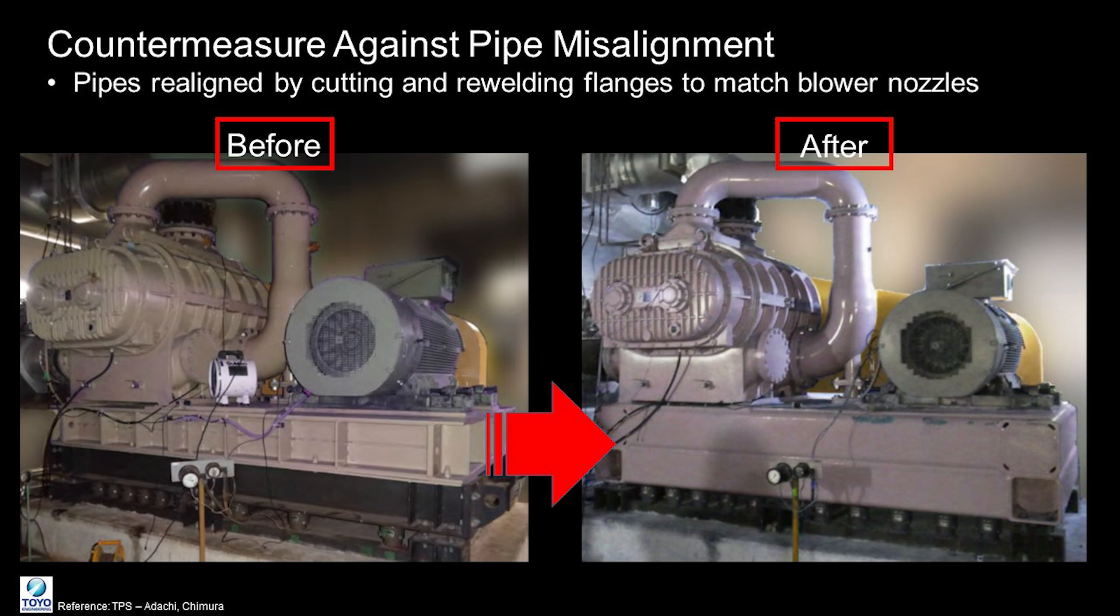To resolve this issue, the pipes were realigned by cutting and re-welding them to ensure the pipe flanges match the blower nozzles. This step was taken with the base plate replacement to address both issues.